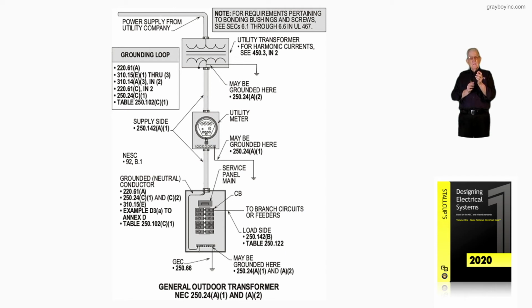And we know that we're told to do that in Chapter 7 of 70B, and to have an effective ground fault path, 250.4(A)(5) tells us the same thing. So we know those are the rules. Now, when we drop down, the National Electrical Safety Code says you've got to ground at the transformers, 92.B.1. That complies with 250.24(A)(2) of the NEC. Now again, 220.61(A) says you carry the unbalanced.